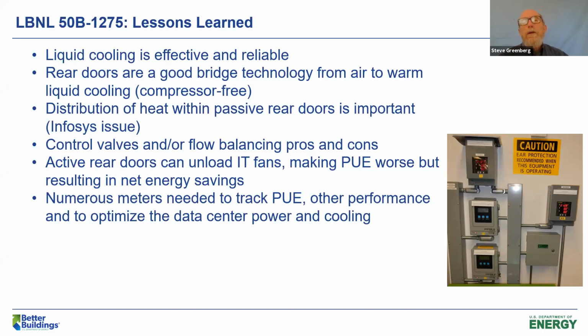Active rear doors add some cooling energy that's not IT energy, but they unload the IT fans, so it makes the PUE worse. Still, there are net energy savings overall.